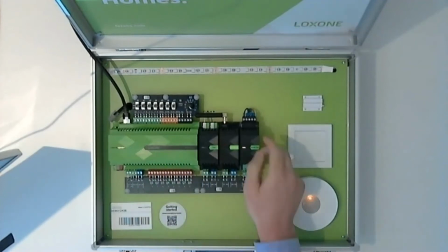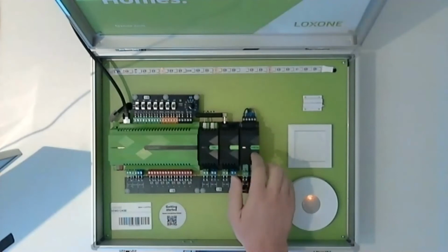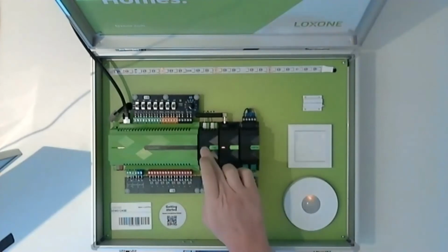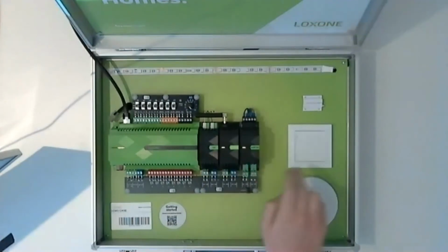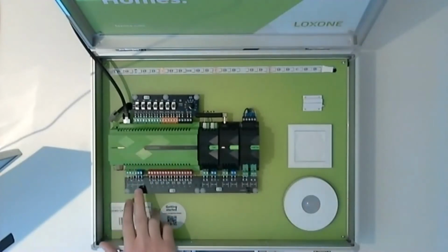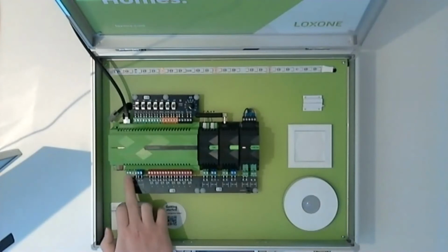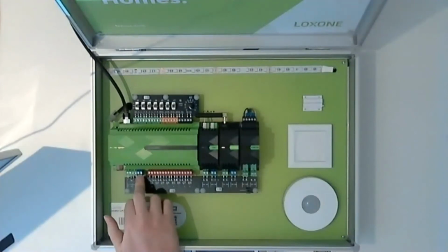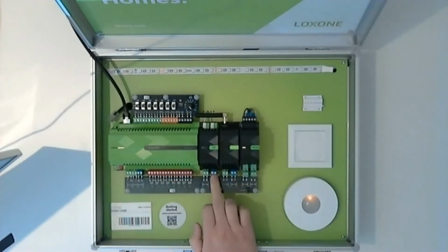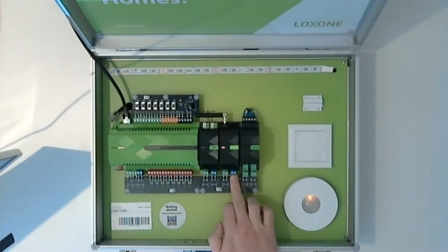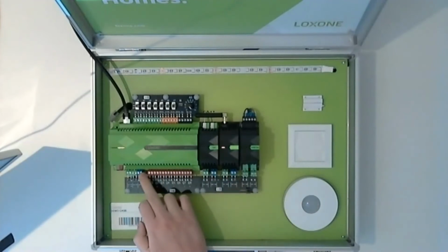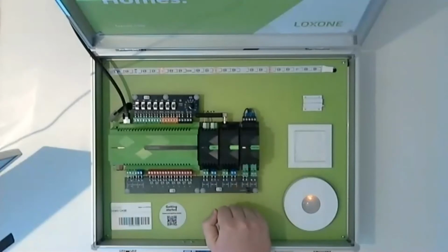And then this dimmer here controls this LED strip at the top, and this is a tree device. So this actually connects to the tree extension here, as do the motion sensor and the touch switch. These are both also tree devices. On the Miniserver, at the bottom, power in. So this is 24 volt DC, power in. The blue connector is the link connector. So for anyone watching the webinar yesterday, link connects the Miniserver to extensions. So you'll also see this same blue connector on the tree and on the airbase extension as well. So the three of those are connected together to connect the Miniserver to the extensions.